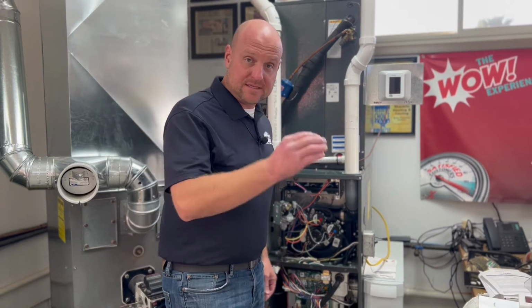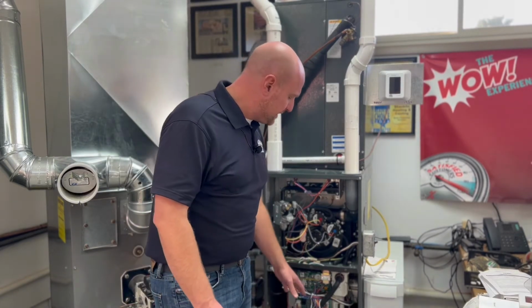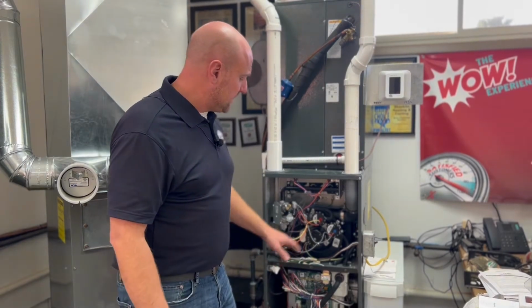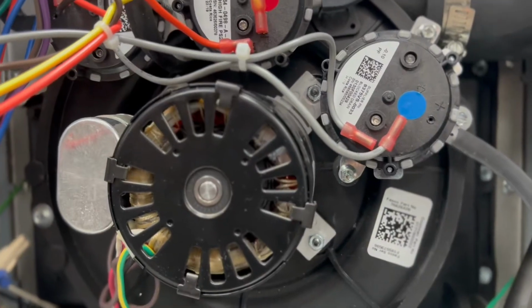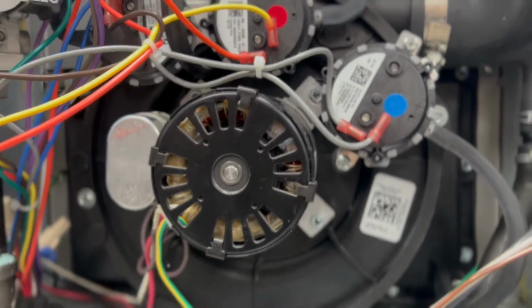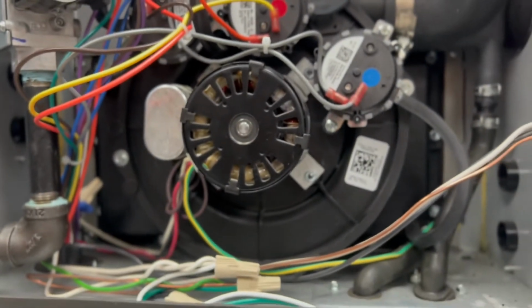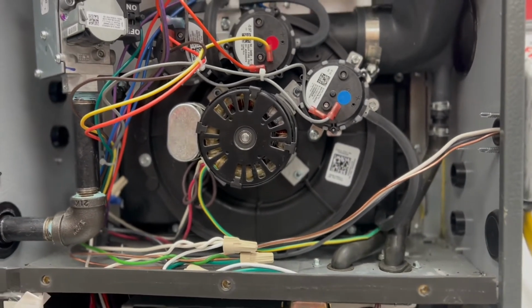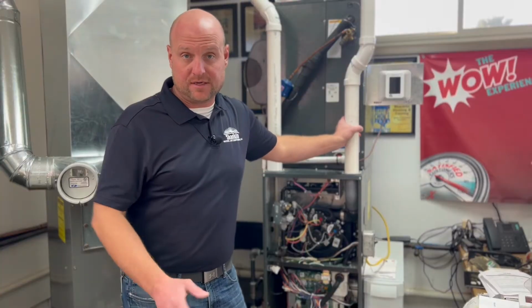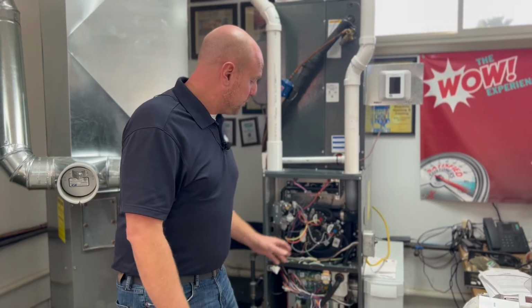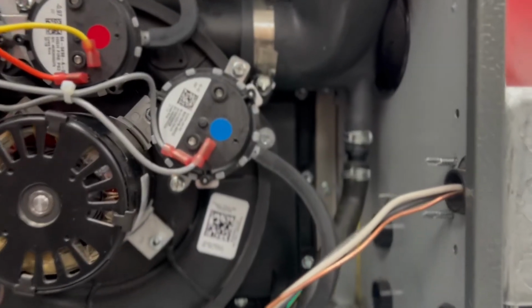Once it receives that signal to turn on, it is then going to send 120 volts up to the draft inducer. The draft inducer is going to turn on and come up to full speed. Its purpose is to clear any flue gases out of the heat exchanger and make sure the vent pipes are free of any obstructions. At this point, the pressure switches here are going to prove that.